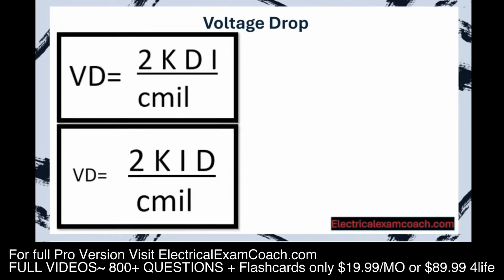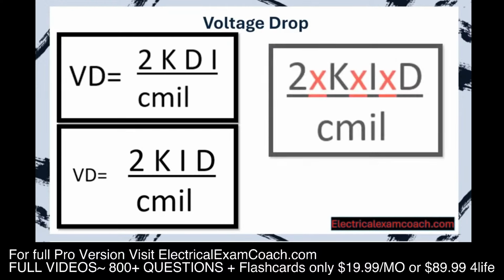I do it like this. 2 K I D over C mil. Easy to remember and easy to plug in. And what this is, just like previously in the program, this is implied multiplication. So it's going to be 2 multiplied by K, multiplied by I, multiplied by D, divided by C mils. Now let's learn what each one of these individual pieces mean.